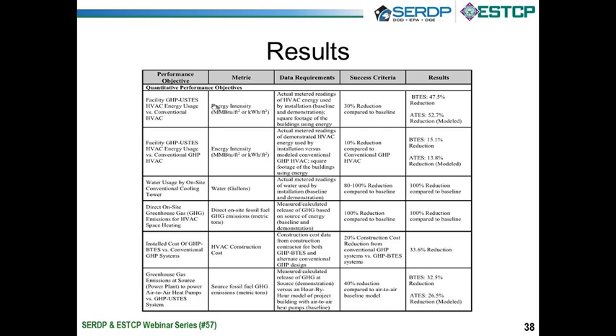And be aware that when you're in a deep south climate like we are, or even a very cold climate, anywhere where the loads aren't balanced, if you do it right and you want the system to last for 30 years, and all you're doing in the long run is putting more heat in the ground than you're taking out, it's going to warm up. So there are plenty of systems out there that screw up, but it's only because they weren't engineered properly and they weren't modeled properly and they put more heat in the ground or took more heat out of the ground than the system could stand. But the science is pretty settled on this. If you do it right, these systems can last a long time.